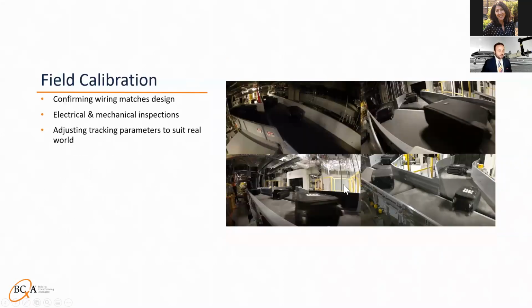Once a system's been built, the controls engineers go out and start calibrating the system. The actual conveyors are slightly different than those that are emulated, and then they'll have to recalibrate some of the tracking parameters. Sometimes there's belt slip, or the tension might vary some of the different pulses per foot. They'll also confirm that the wiring matches the design. So as they go through and check each of the conveyors, if you flag the right photo eye and the correct conveyor starts, it'll be readily obvious that they've been wired correctly.